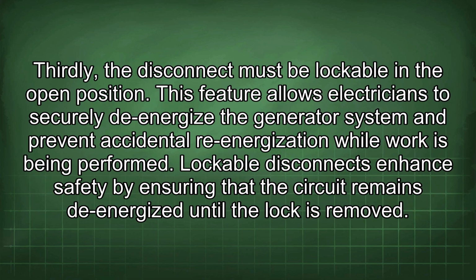Thirdly, the disconnect must be lockable in the open position. This feature allows electricians to securely de-energize the generator system and prevent accidental re-energization while work is being performed. Lockable disconnects enhance safety by ensuring that the circuit remains de-energized until the lock is removed.